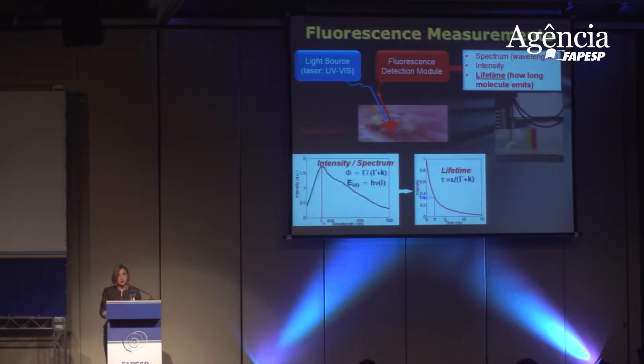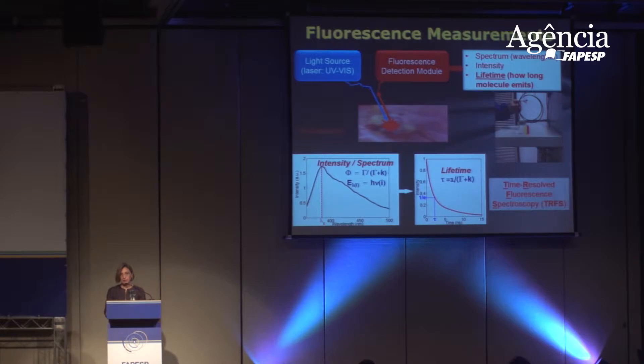There are several ways of measuring this fluorescence emission. Either you can look at the spectrum of emission — the wavelength, the color of light — or you can look at the intensity of emission, or what is called fluorescence lifetime, meaning for how long these molecules will emit. Most of the instruments which have made it to clinical settings and some commercially available devices are based on intensity and spectrum measurements, looking at the quantum yield of these molecules or how the emission is distributed along the spectrum. But very few are actually based on fluorescence lifetime, which measures the excited state lifetime — how long a molecule will spend in the excited state.